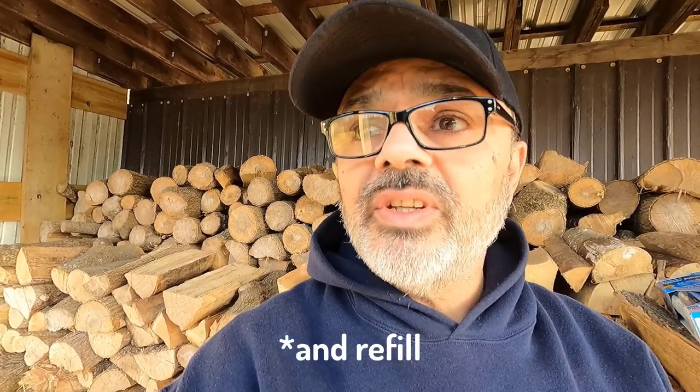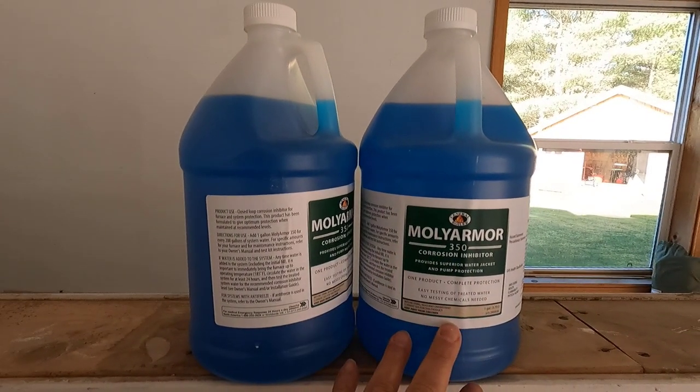Some people normally change the water in the spring at the end of the wood-burning season — they add a sludge conditioner, run it for five days, drain the water, and add the MolyArmor rust inhibitor. But in this case, the previous owner told me he normally adds the rust inhibitor at the beginning of the burning season, and that's what I'm going to do now. Come this spring, I want to add the sludge conditioner, run it five to seven days, drain it, fill it back up, and add new rust inhibitor.